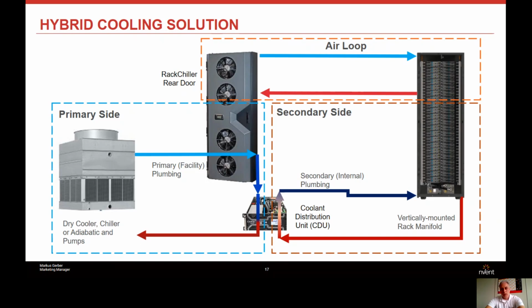Then you have a return liquid temperature. And this return temperature goes to the CDU. Because, as mentioned before, on the cold plate on the server level, you don't need really low temperatures on the liquid side. So this return temperature is enough to cool the server side. And then what you achieve is a higher delta T on your facility side, and that helps getting efficient. Now I hope this was clear.